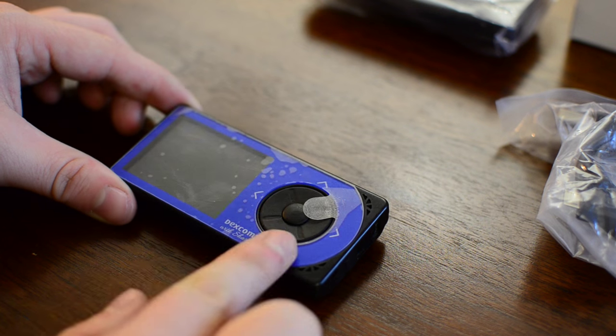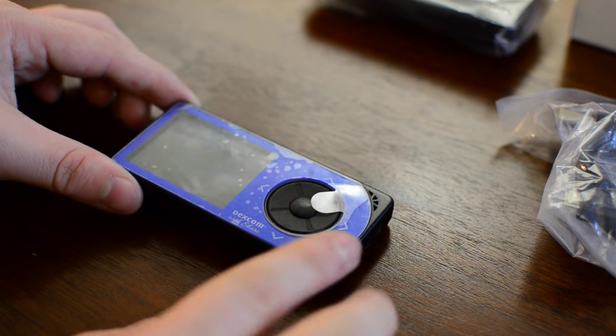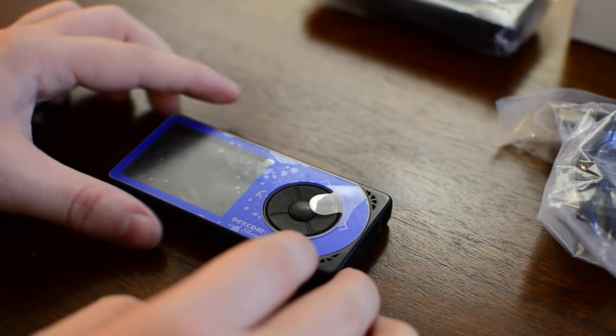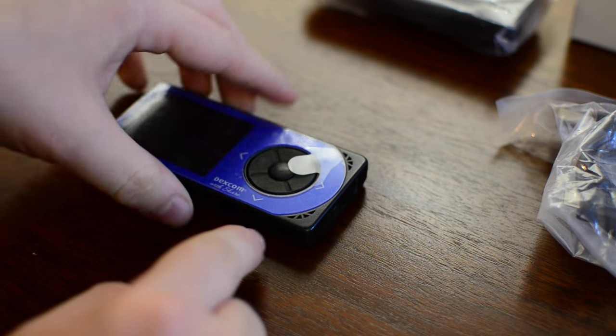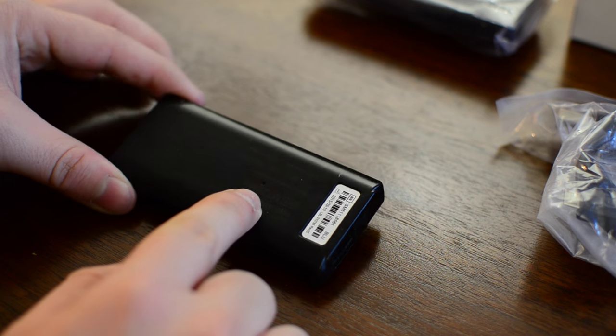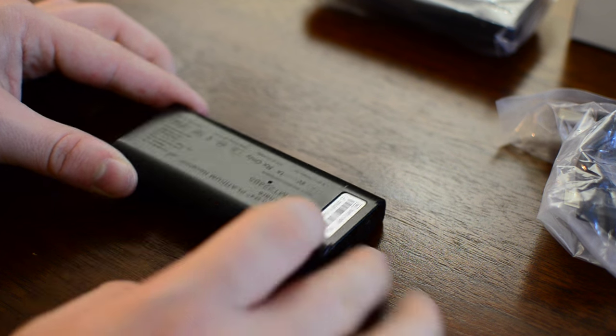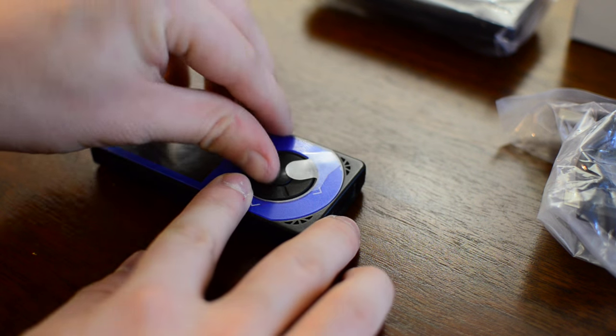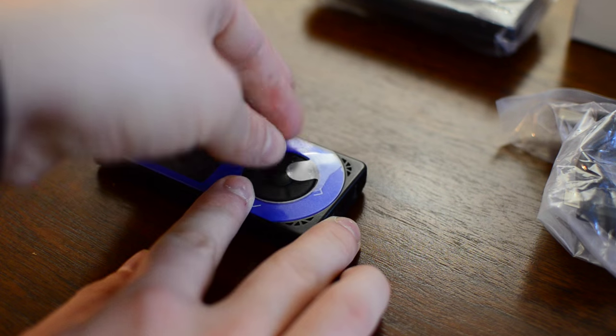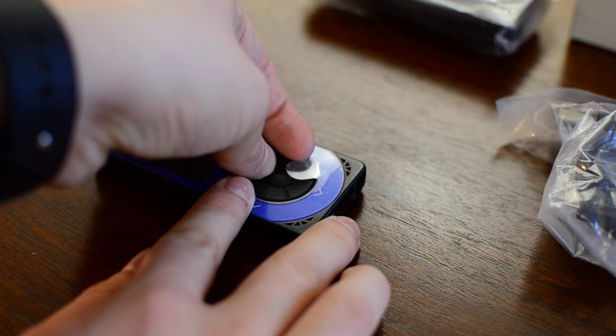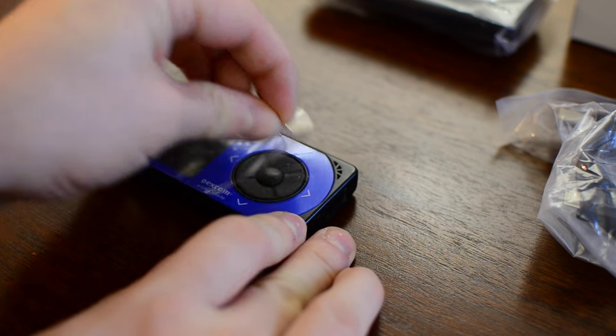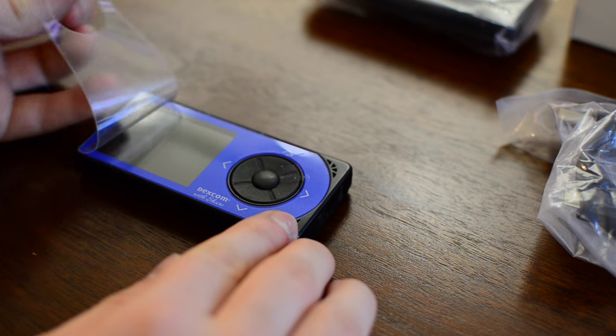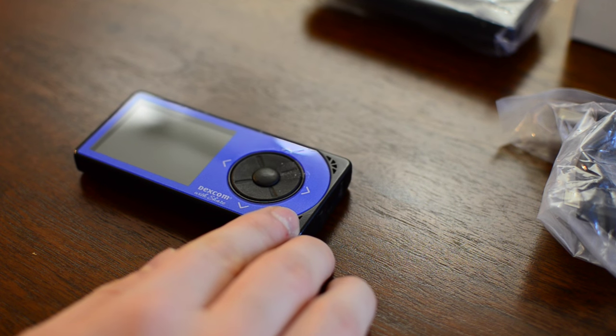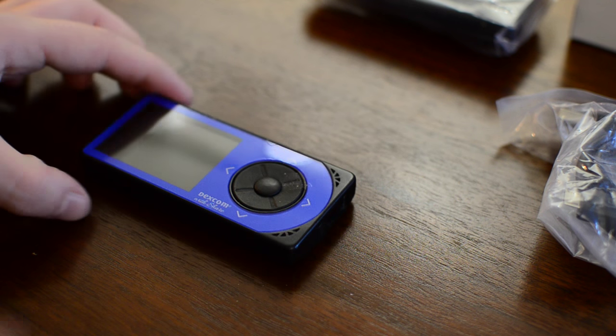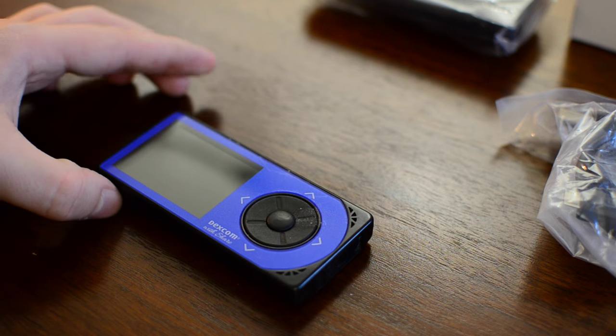So if we look at the receiver itself, there's one big difference with, say, the Enlite, which goes straight to the Medtronic pump. This actually requires the separate receiver. It's a fairly basic unit. There's a reset button on the back that'll reset the communications if it ever has problems communicating with the sensor or with your phone. There's simple material here on front to cover the screen. There are speakers built in, so obviously if you are going low, say in the middle of the night, it can start beeping wildly at you, telling you to wake up, you're going low. So there is a lot of basic stuff like that.